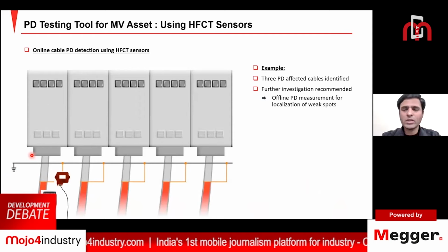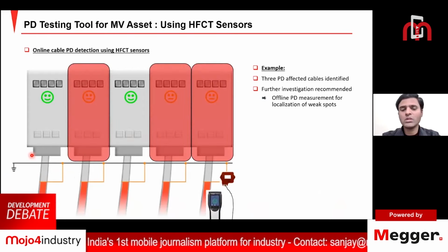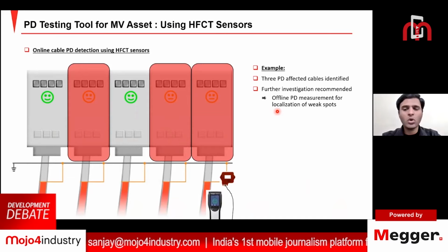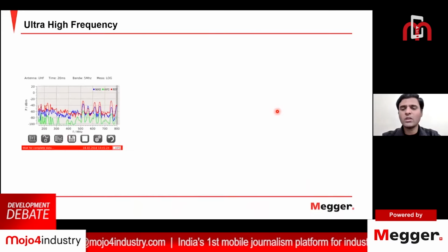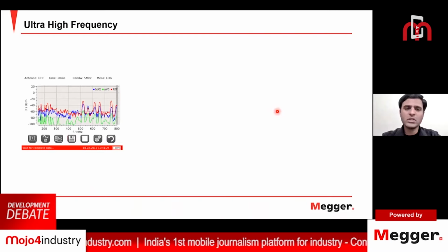HFCTs can be used at the cable terminations, which will help you to identify, from among a number of cable terminations or cables, which one is a suspected one. And you can go for an offline shutdown of that particular cable and do an offline PD measurement to localize the weak spots along the length of the cable. So online PD detection is very well used and very well accepted. On different electrical assets, different sensors are used.